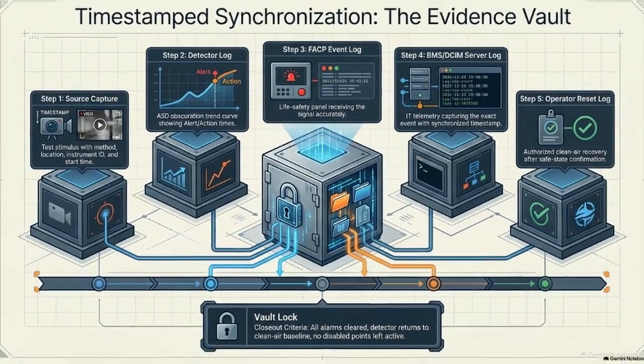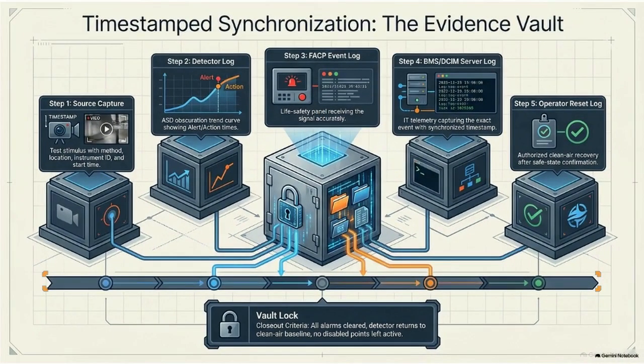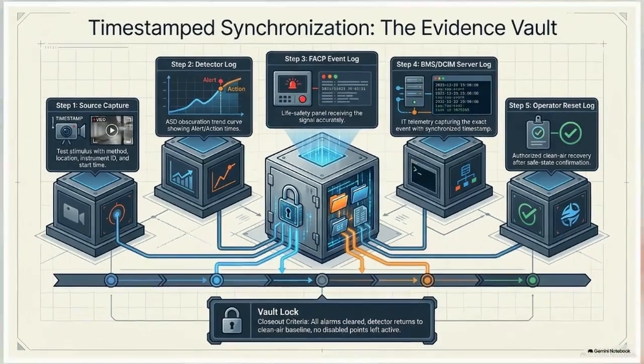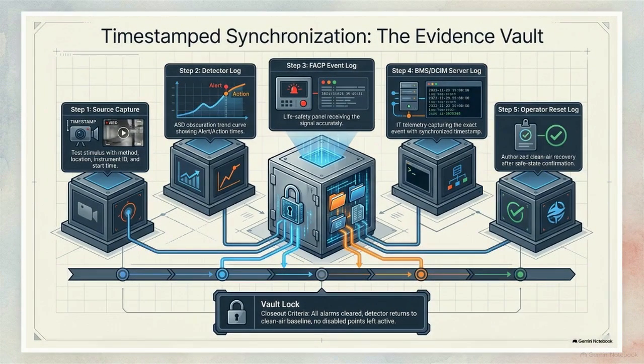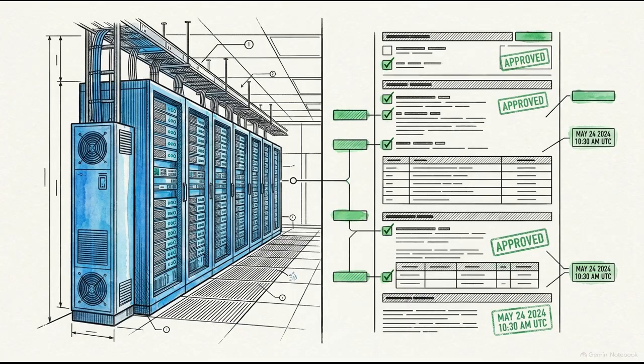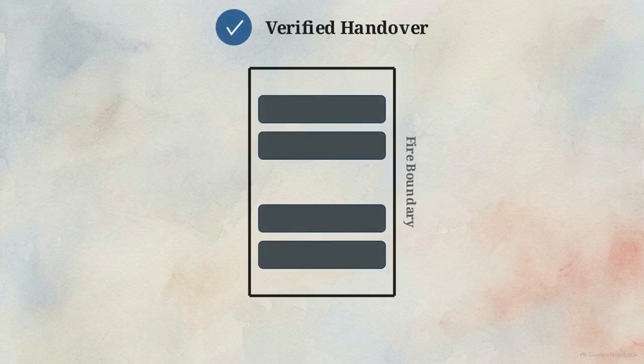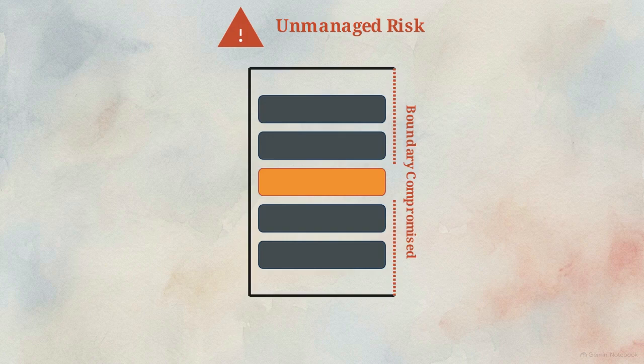Every action an operator takes and every response the system generates must be logged for post-incident audits in what we call the evidence vault. This timeline shows the strict chronological synchronization required to prove compliance. The timestamp of the source stimulus must align with the detector log, the FACP event, the server log, and finally the operator's authorized reset. The most advanced engineering in the world is useless if the human operational response isn't scripted, disciplined, and forensically timestamped. Even after a perfect handover, facilities degrade, standards update, and owners face constant commercial pressure to modify layouts for better uptime.